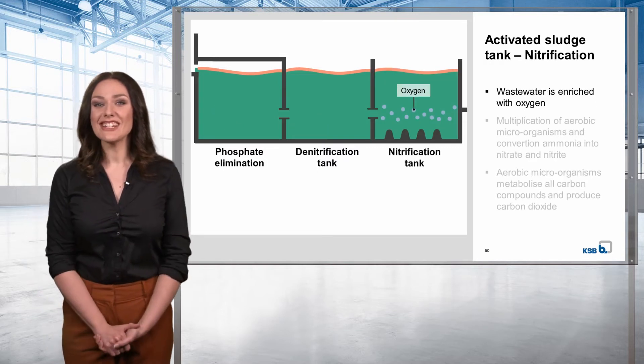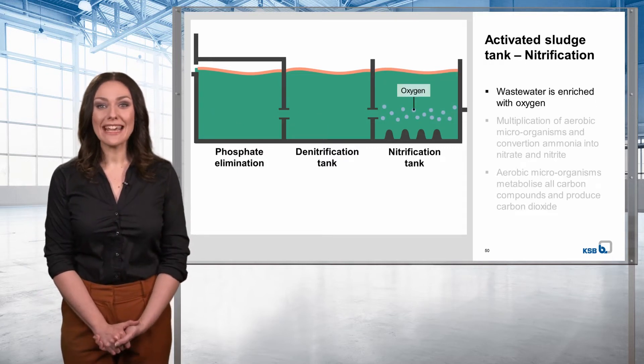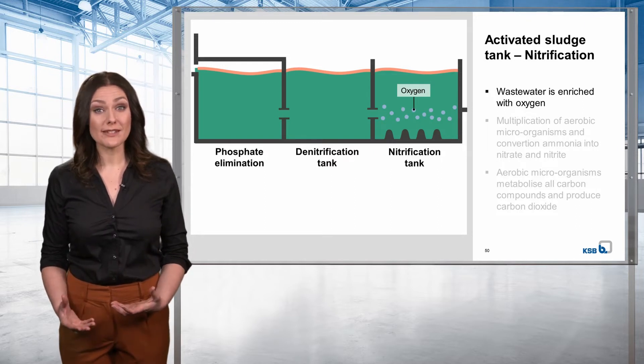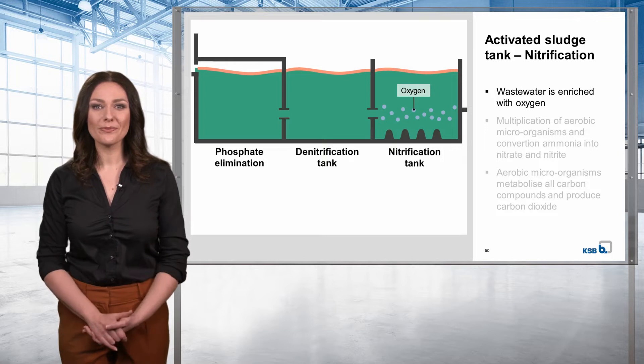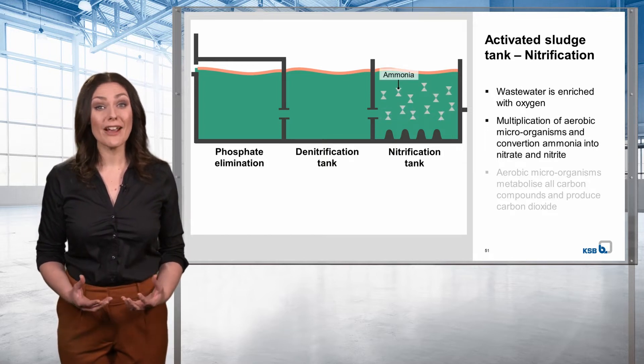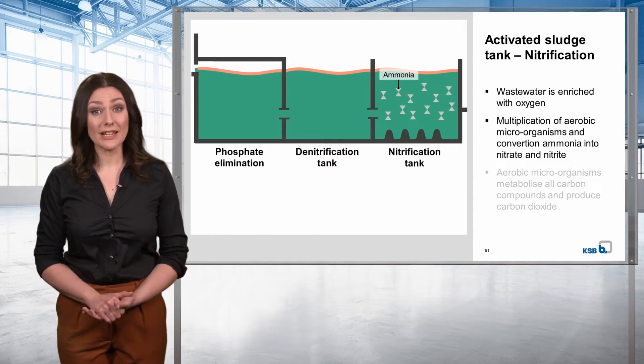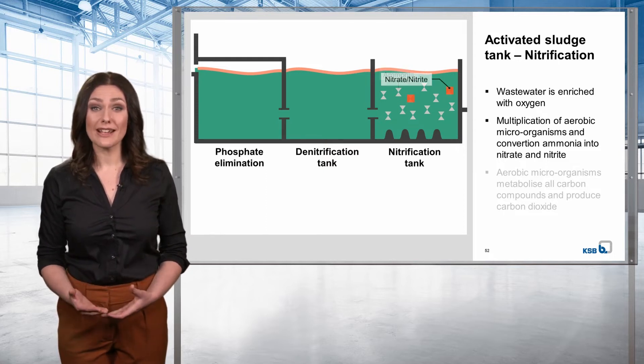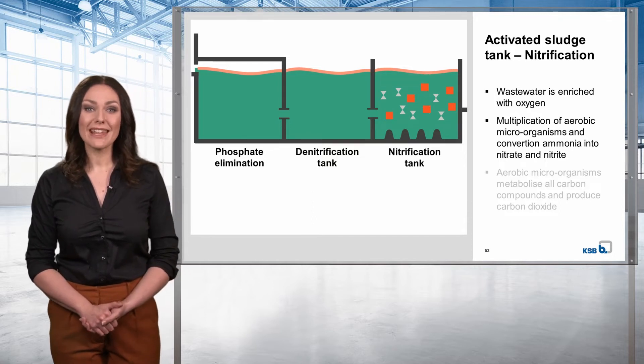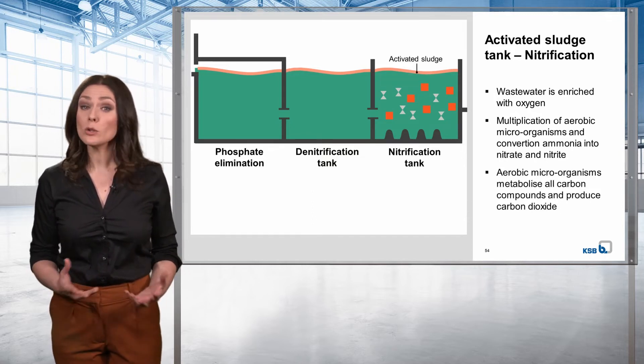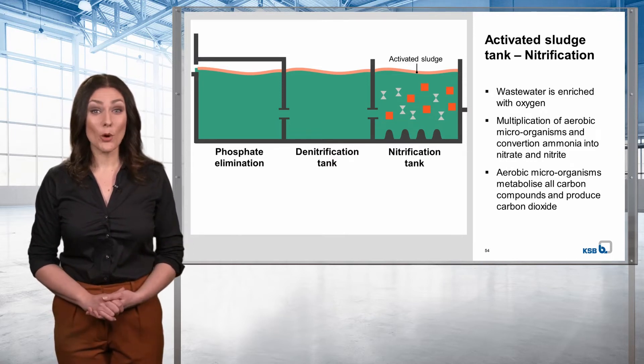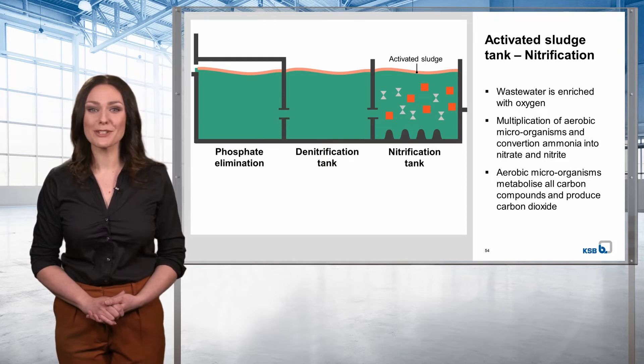The last stage is that of nitrification. Here, the wastewater is enriched with oxygen that is supplied by aeration units that are usually fitted to the floor. This creates a favorable environment for aerobic microorganisms that convert ammonia, or urine, into nitrate and nitrite — also referred to as nitrification. They also metabolize all carbon compounds and produce carbon dioxide. In these conditions, the aerobic microorganisms keep multiplying.